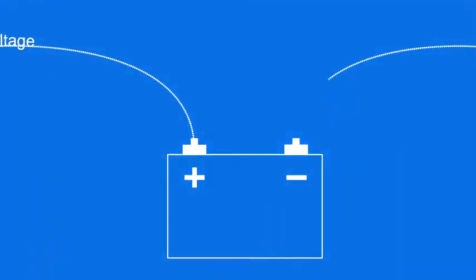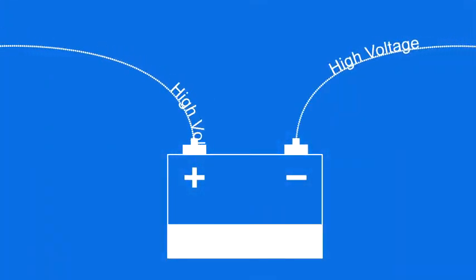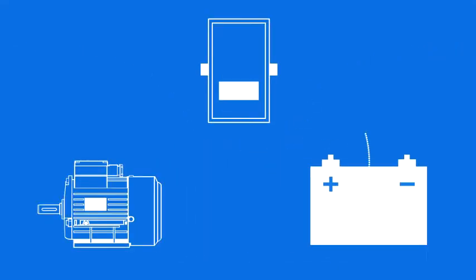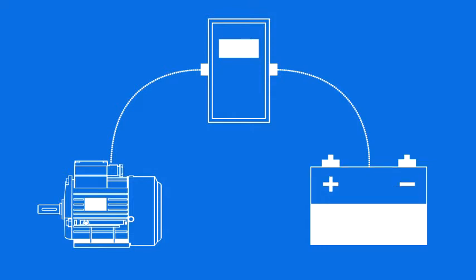In concept, to run a surge test, charge a small battery or capacitor up to several thousand volts, then connect it to the motor winding through a switch. When the switch is closed, a large amount of current flows into the winding, causing a voltage to appear across the wire insulation. This voltage is due primarily to the inductance of the winding. The battery quickly discharges and the whole surge test is done in a few microseconds.